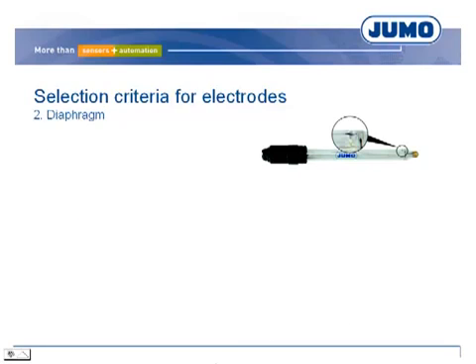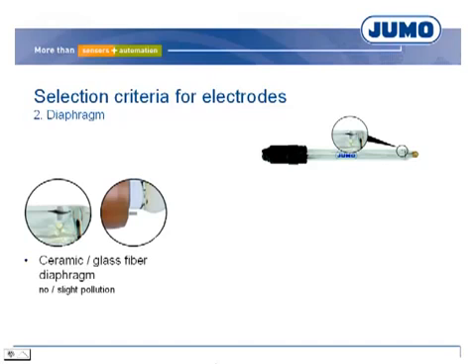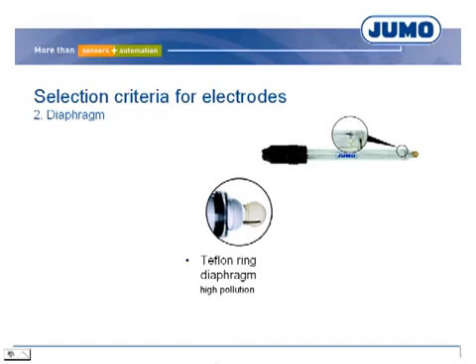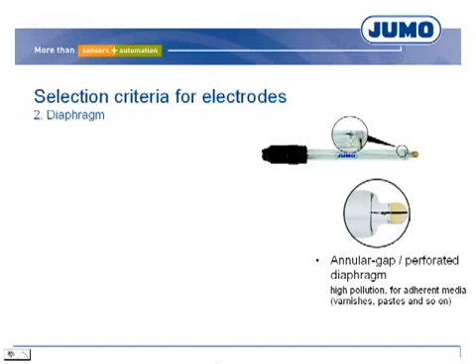Using the right diaphragm for the application is very important. When the medium is not or only slightly polluted, the ceramic or glass fiber diaphragm can be used. For high pollution, such as wastewater applications, the Teflon ring diaphragm enables a larger connection between medium and reference electrolyte, and particles can adhere to the Teflon only rarely — it has a self-cleaning effect. Annular gap or perforated diaphragms are used with a solid electrolyte for media with high pollution or adherent media like varnishes or pastes.